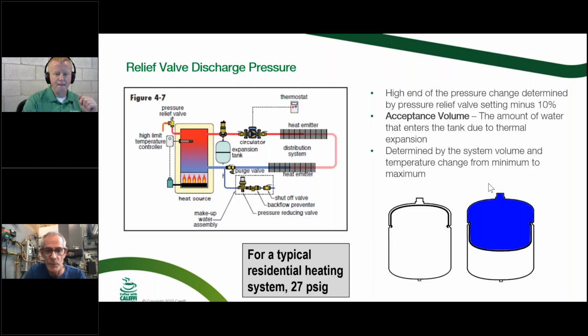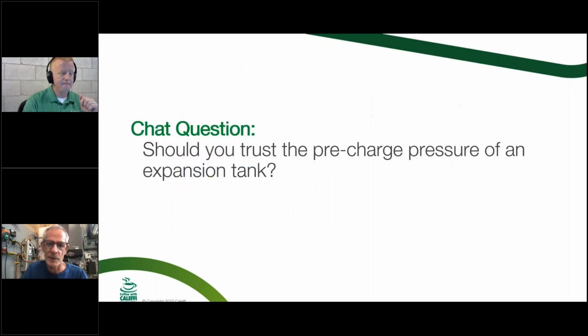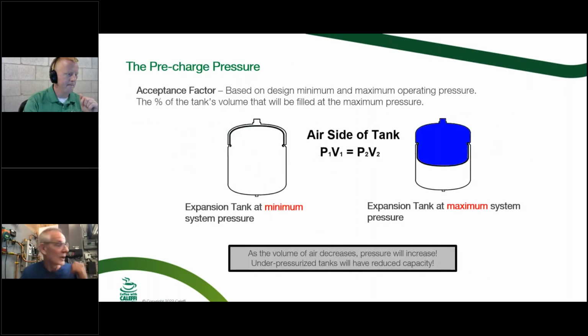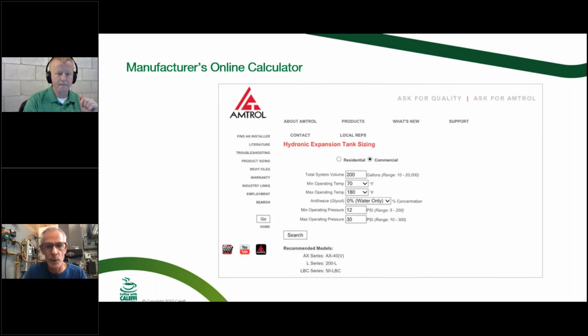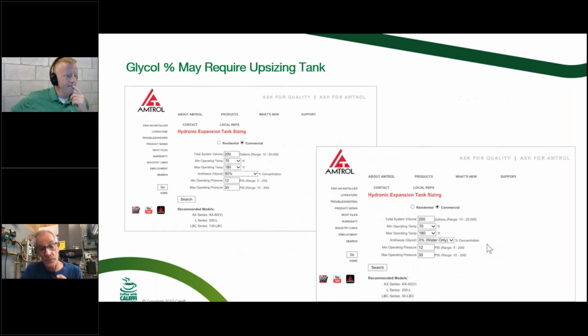No, that's exactly it. I mean, whatever you're willing to accept before your relief valve, or whatever the pressure rating on your boiler is. Most of them are 30 pounds. Some of the commercial boilers, or even some of the residentials, this one behind me will allow you to go up to a 45 psi pressure relief valve. But again, you put into the formula here what your acceptable pressure range is, and your temperature swing, and that one just shows water. And the reason I put this one in is on the next slide, I think, Cody, I show it with glycol. It makes a big difference.